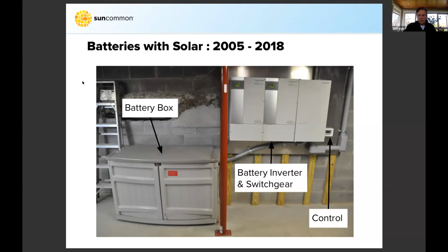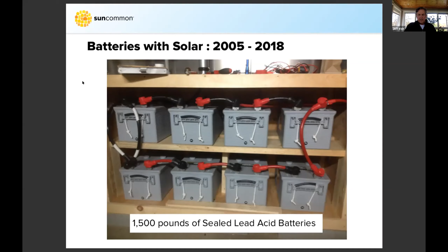Inside that battery box, it looked like this. There were, in our typical systems, about 1,500 pounds of sealed lead acid batteries. Sealed, meaning they were maintenance free. You didn't need to add electrolyte or solution to them every month like you do with flooded batteries. So they're pretty safe and pretty reliable, but there were a lot of them and they were big. 1,500 pounds is a lot of batteries, and we were also limited in the technology, you couldn't really put many more batteries together than the 8 you see here. You could maybe go up to 12, but that was about it.